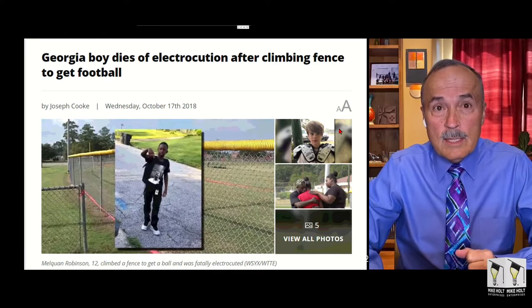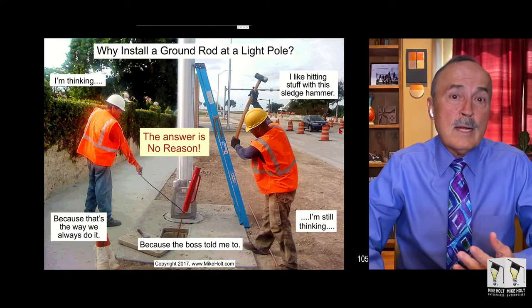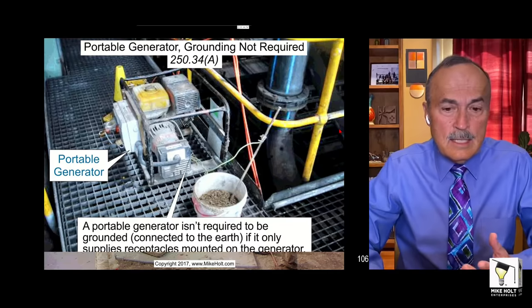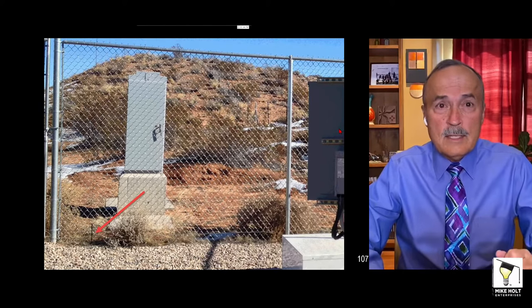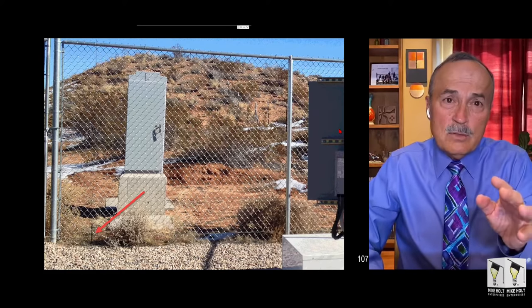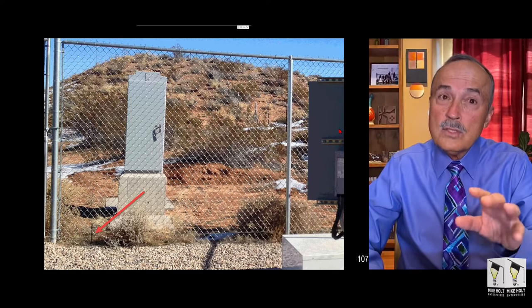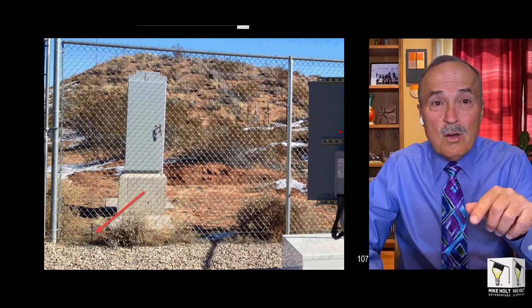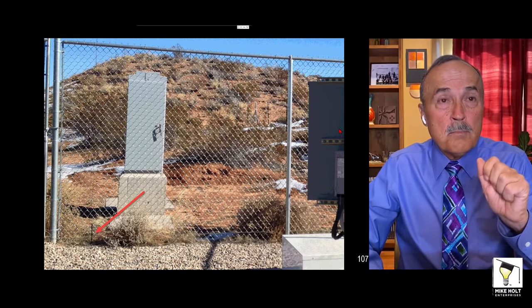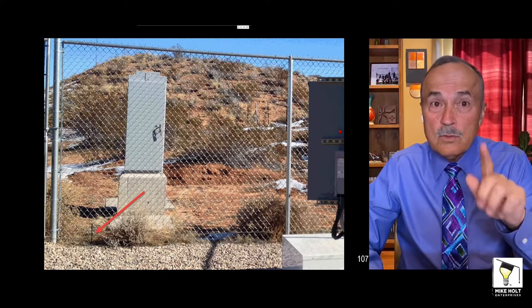So we watched that video and talked about why that young boy got killed. People drive ground rods for a reason - crazy concepts of grounding. Fences with ground rods in them. It's not illegal to drive ground rods, but the code doesn't require it. It's just not good practice because it gives a false impression of safety, like what killed that young boy. Pretty much all ball field lighting probably has no equipment grounding conductor and probably has ground rods - so don't be touching ball field lighting.